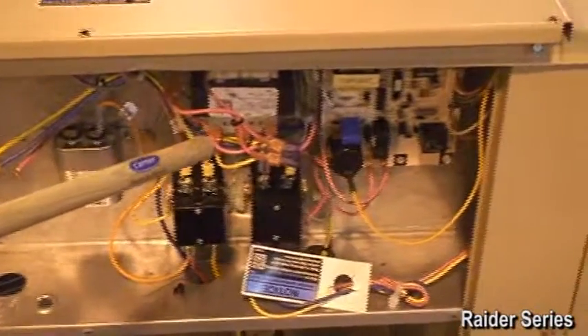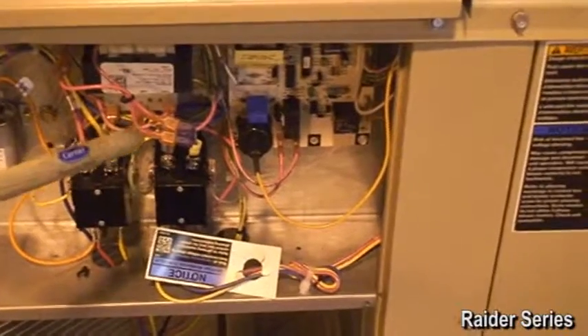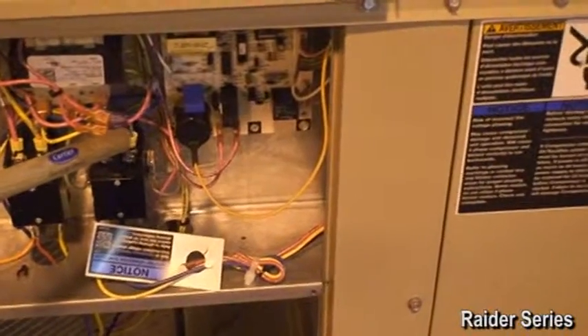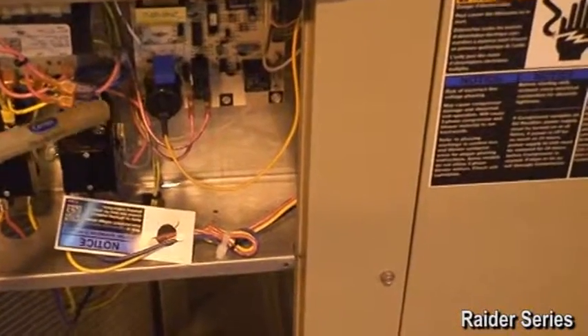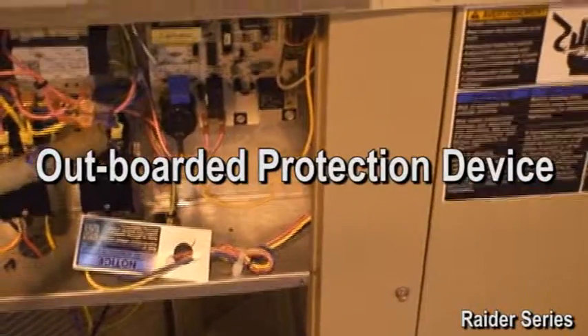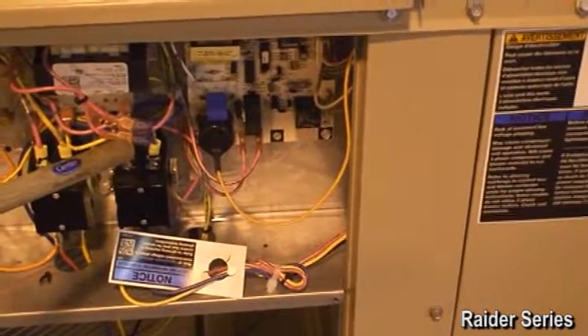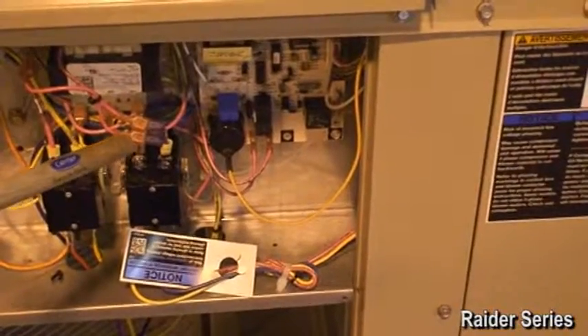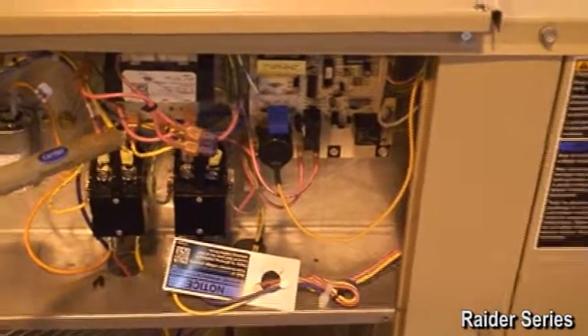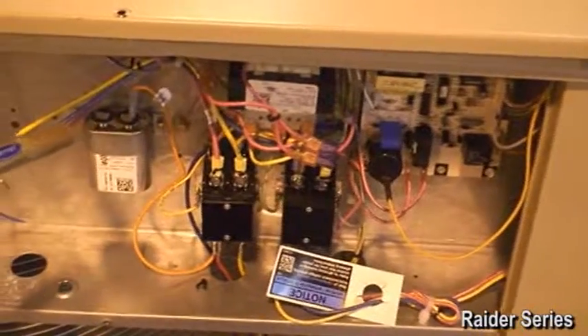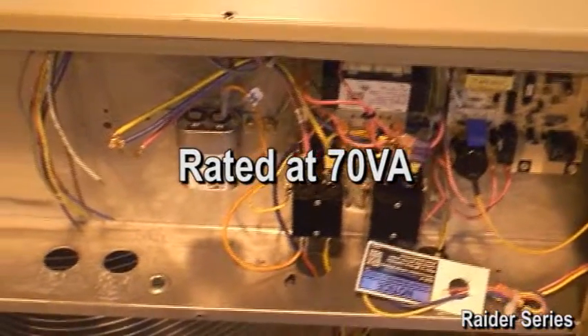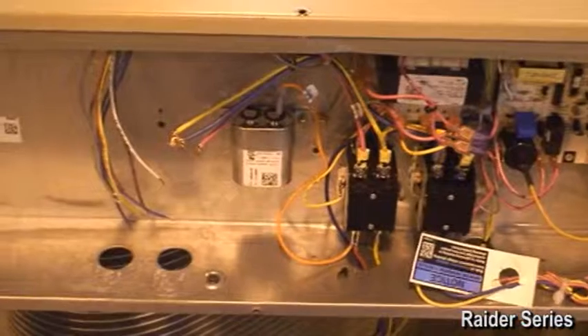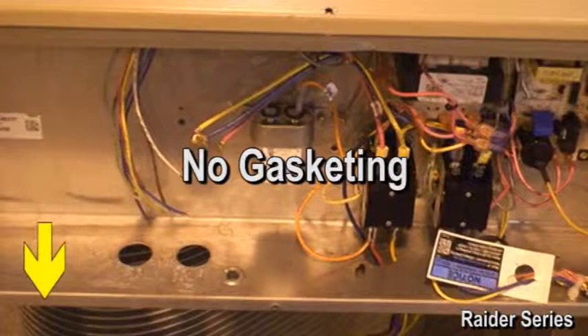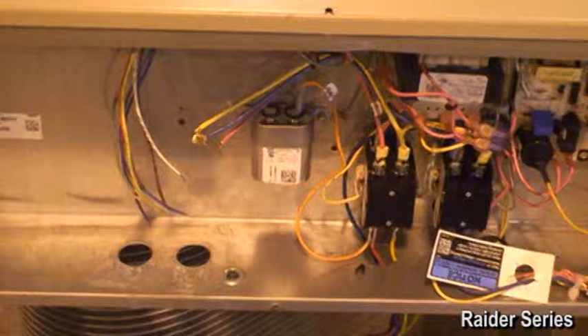Moving over to the unit transformer, you will see that the transformer protection is here and uses an automotive blade type fuse. What our review team noticed is that an outboarded protection device like this will not protect the transformer when someone wires directly to the transformer's 24-volt side, which is a common practice. The transformer is also only rated at 70 VA. Here you will also notice there is no gasketing between the metal door and the control box, which can lead to contaminants like snow, dust, rain, and cottonwood entering the control box.